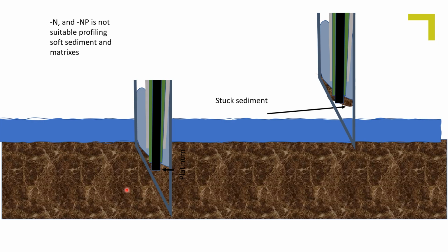Needle-embedded sensors might seem like an attractive model for profiling due to the protection of the glass tip. However, this protection makes them unsuitable for profiling, especially in soft and organic matrices, due to the cavity between the sensor/electrode tip and the needle protection. This schematic illustration of a redox or ORP needle electrode tip is pointing out the problem. The cavity significantly limits the applicability for profiling in biologically active matrices, as the material will be pushed into the cavity and might be stuck there.